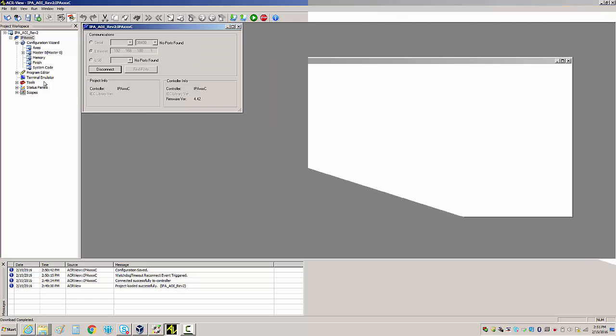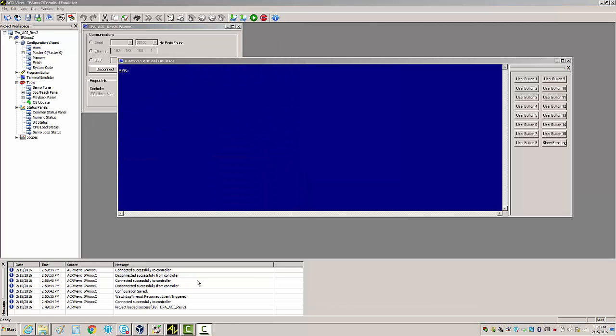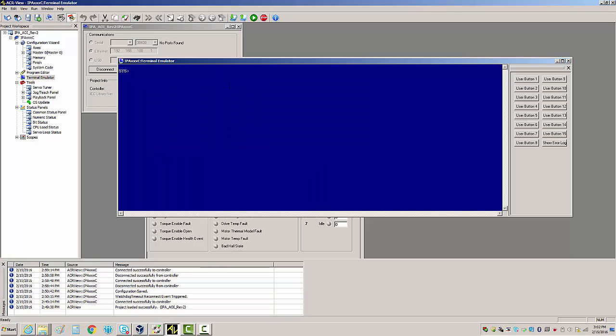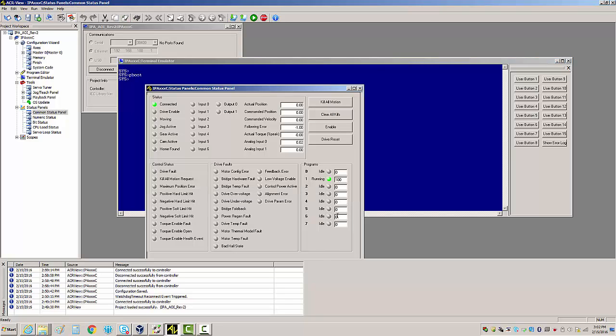Press OK. Now in ACR view, if you look at the common status panel, you'll notice that the programs aren't running. We didn't cycle power, so if you go to the terminal window, you can just type pboot and that will automatically start running all power up programs.